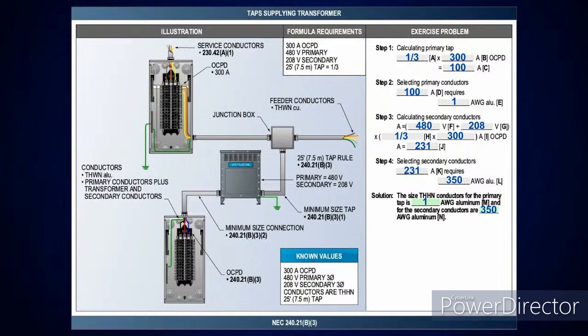Now, when I look at calculating the secondary conductors here, I need the ratio of the transformer. So I'm just going to take the 208 volts divided into the 480 volts. Then I'm going to multiply from that point a third and the 300 amp overcurrent device. That's going to give you 231 amps. The next size up above that is a 350 kcmil aluminum. So as you can see, doesn't matter what you're doing, which conductors you're using here. All you have to remember when you're doing these calculations is if it's 10 foot or less, divide by 10. Everything else, take it a third. And if I have a transformer in the tap, I got to get the ratio of the transformer on the secondary. That's it.